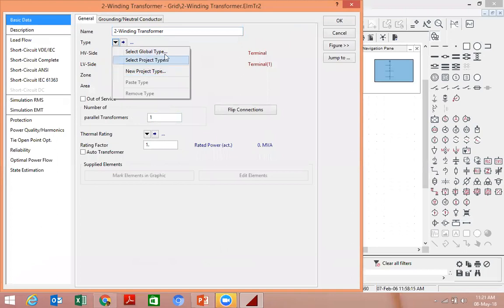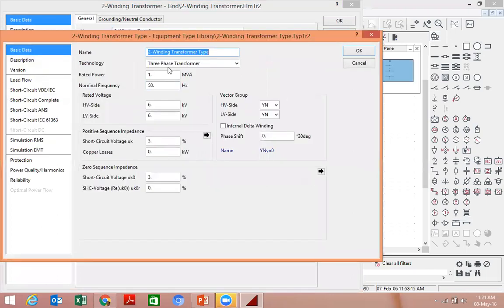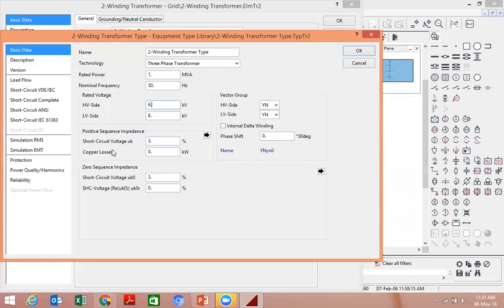If we go with the new project type, what we do is specify the rated power, rated nominal frequency, high voltage and low voltage side values. We can also introduce these things I've discussed in the previous session. I'm just showing you for better understanding. And then vector groups also, you can specify high voltage, low voltage values, positive sequence impedance, short circuit voltage, copper losses, and all such things.